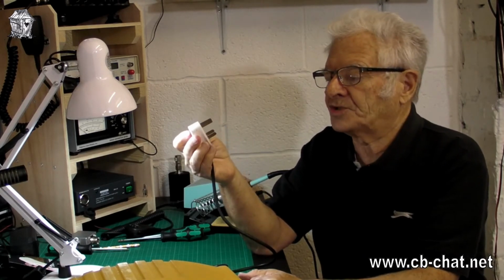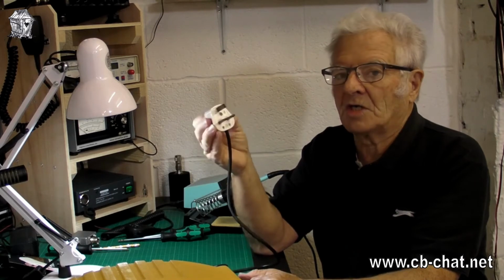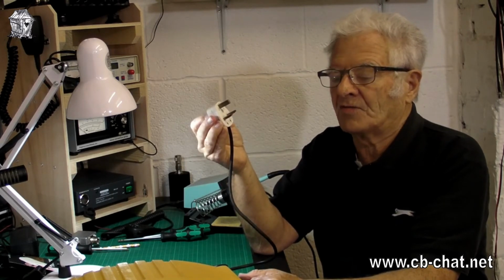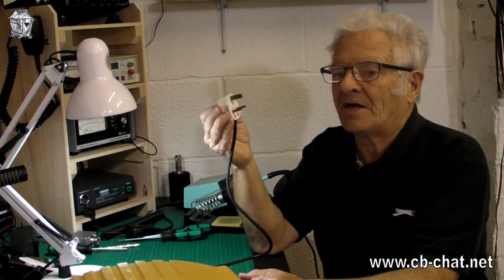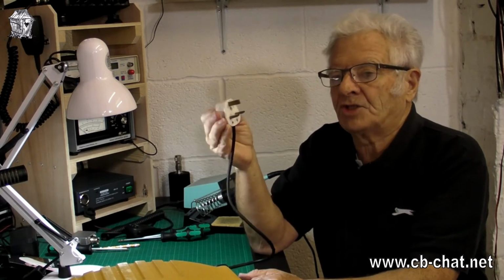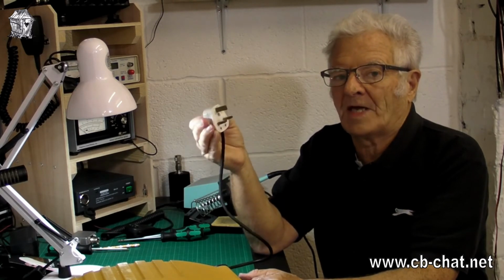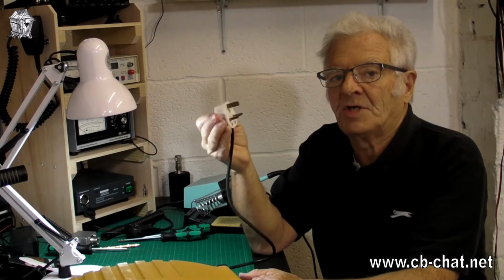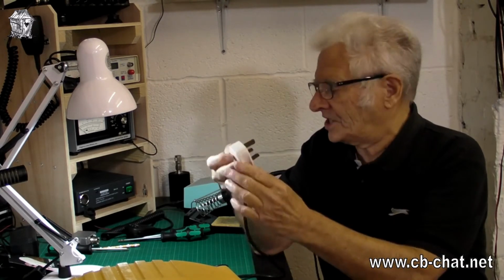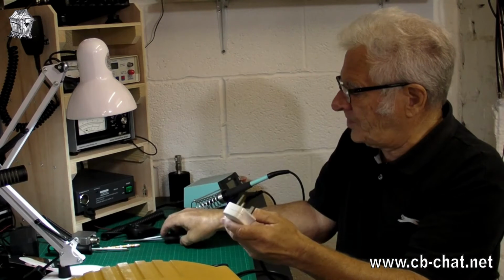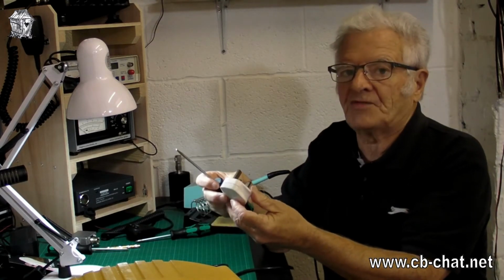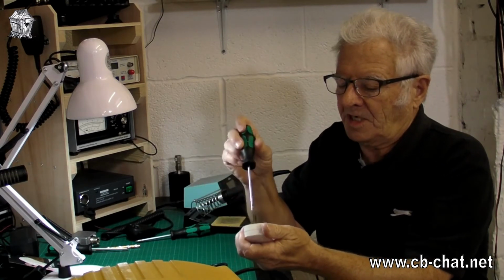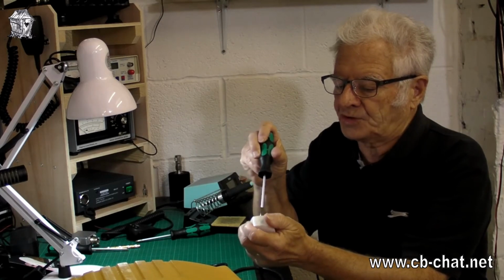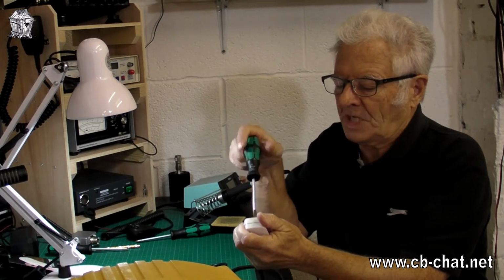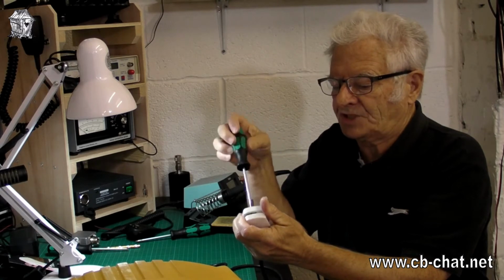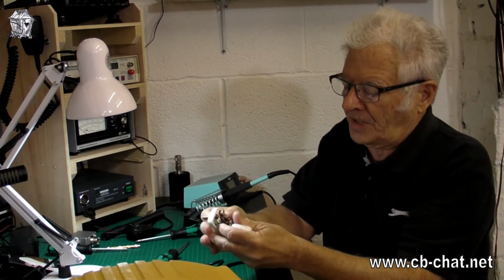You should warn the person that's got it that this is no longer current as far as safety measures, and advise them to change it as soon as possible. They don't have to, you wouldn't fail it, but you advise them that really you should look at changing this. So that's the first thing. Now the next thing we've got to do is check the fuse in it, to see if it's got the right value fuse. I thought I was going to struggle to unscrew this, but it's quite loose.